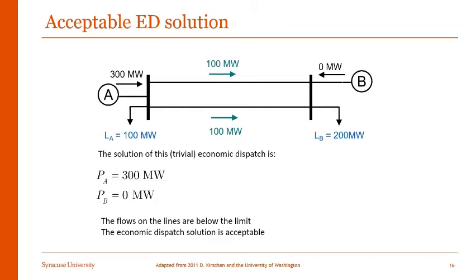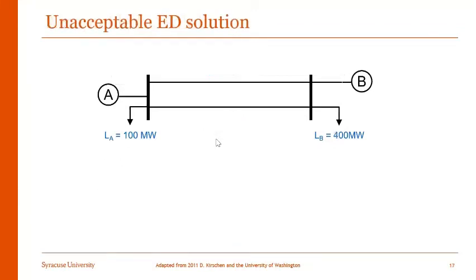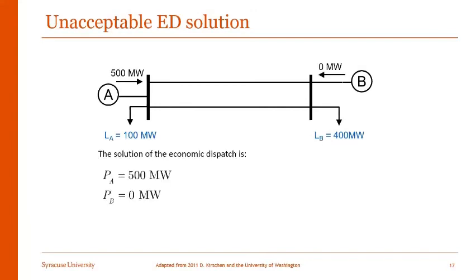We'll see what happens when load increases and we still continue generating from generator A. In the next picture, load at bus B increases from 200 to 400. Now the solution of economic dispatch becomes 500 megawatts at generator A and 0 megawatts at generator B, again following the rule that A is less expensive and B is more expensive. In this case, we see the line power flows are both 200 megawatts.